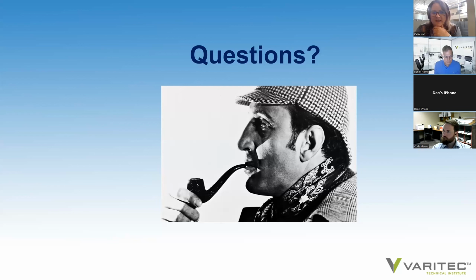Okay, so next question. I'm guessing this assumes regional higher humidity areas. I did not see any humidifier impacts or costs. We did not incorporate humidifier impacts or costs in the study. It is certainly an option that you would want to look at, because our driest time of year is during our winter months. Certainly in Maricopa, it's from November right the way through February. That's our driest time of year. And it would be easy enough to provide an adiabatic atomizing humidification solution into the DOAS component of a space by putting a humidifier grid into the supply air from the DOAS ductwork. So if you wanted to maintain 40 to 60% humidity during our driest times of year, it would be an easy solution. But of course, there's a first cost impact for doing that.